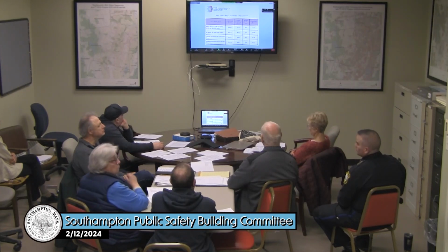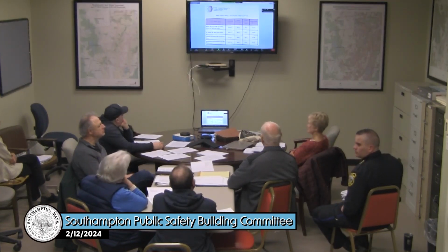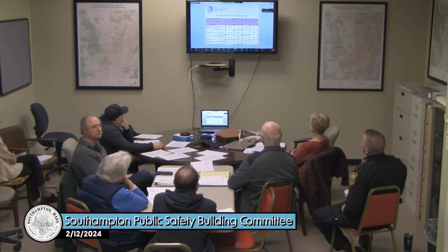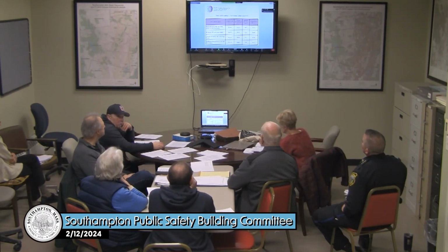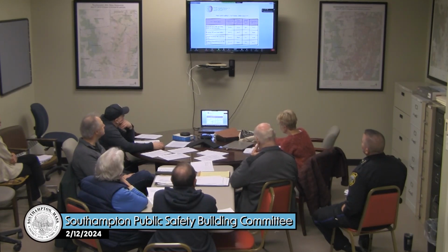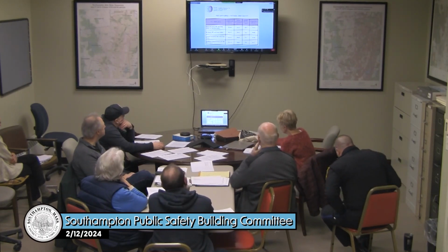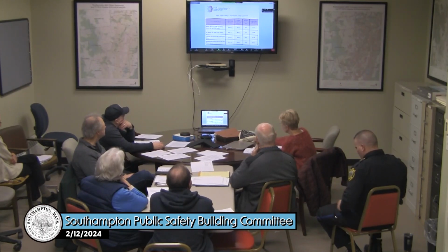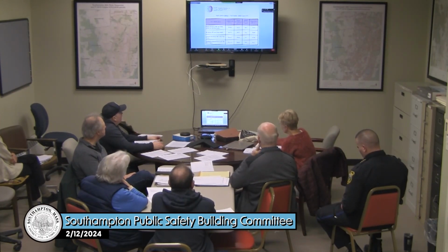And with all the electric heating, does that increase the generator size significantly? It sure does. That's a larger generator, so that's another cost, as opposed to a benefit of a backup gas boiler rather than an electric boiler. The generator for all of these options would be similar, and for any all-electric building, the generator size is similar.